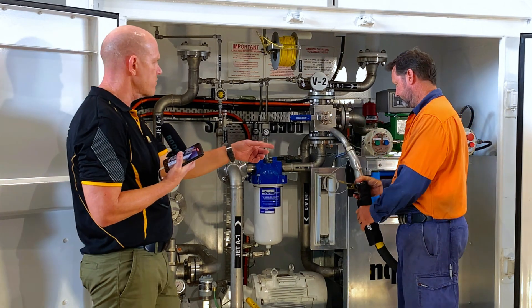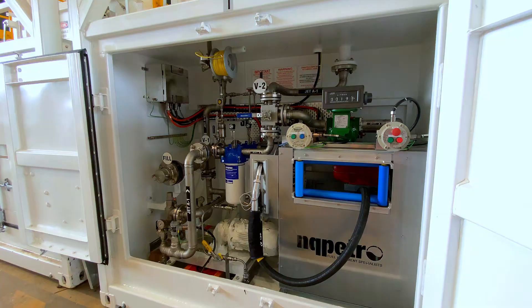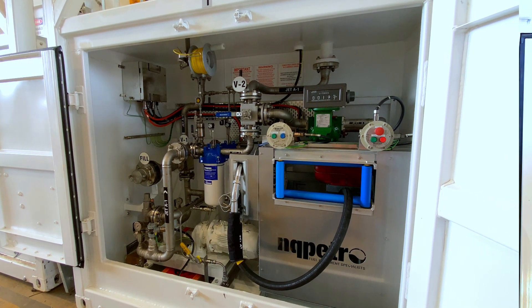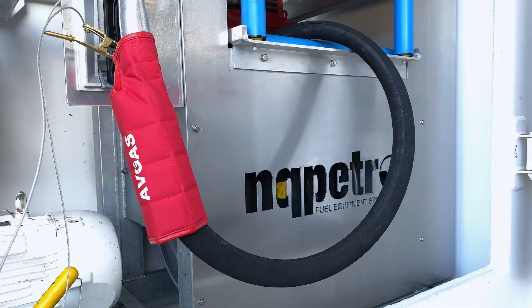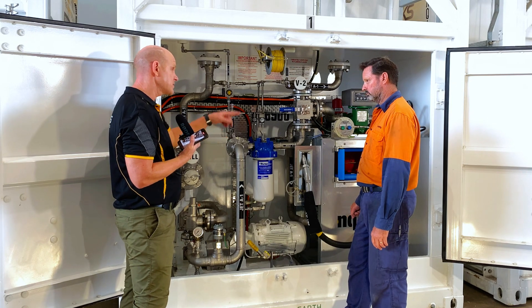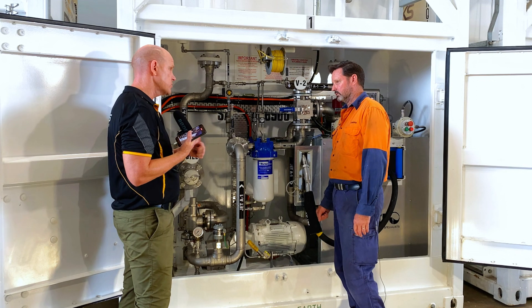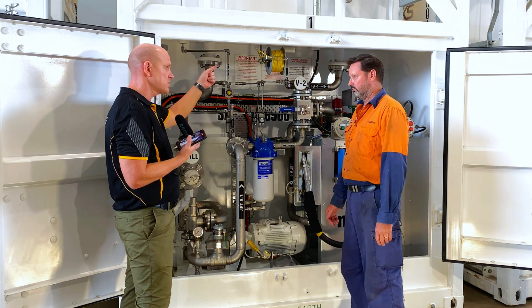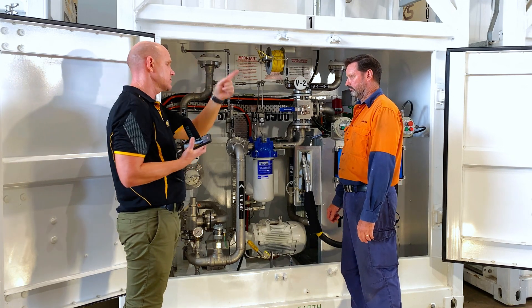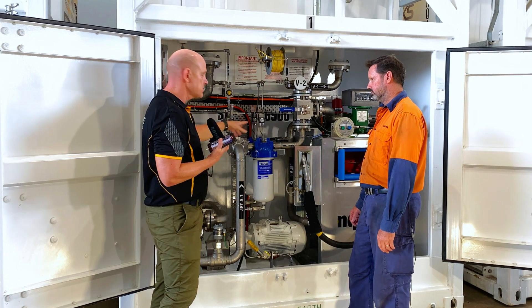What sort of flow rate has this setup got? On the Jet, it's 90 litres a minute. Is the Avgas slightly different? Avgas is 110 litres a minute. In essence, the product is getting filtered twice — the first time when it's coming in from the road tanker and being deposited into the tank, and again when it's being extracted out to go into the aircraft, coming through the same lines and through the filters.